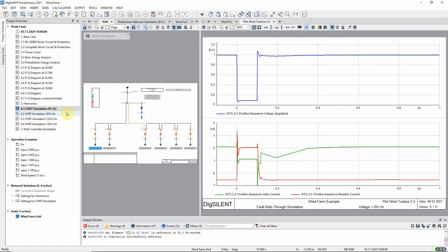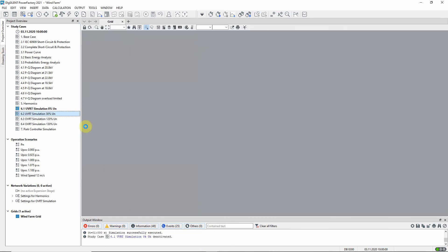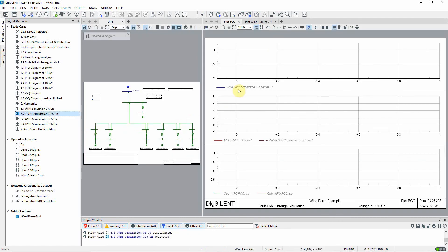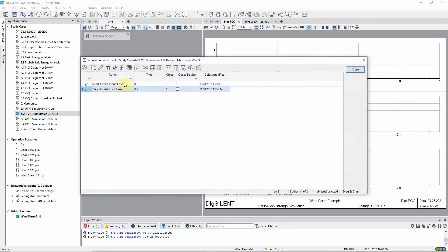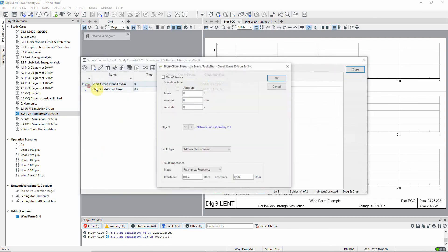Activate study case 6.2. In this study case, a fault is again applied near to the point of common coupling, but a fault impedance is included, which will result in a voltage drop at the point of common coupling to about 30% of its nominal value. This can be seen in the events queue.